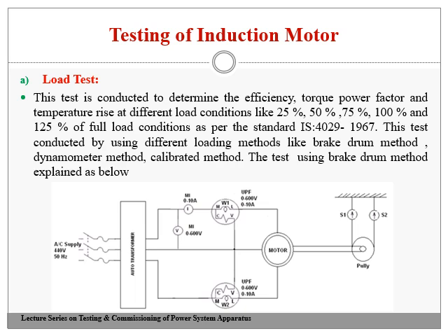When I give the rated voltage, it rotates at the rated speed for which it has been designed, and we note down all the readings: voltmeter, ammeter and two wattmeter readings, as well as the load applied and the speed. This process is repeated for 25%, that is, load the induction motor to 25% of the full load condition using the brake drum arrangement.